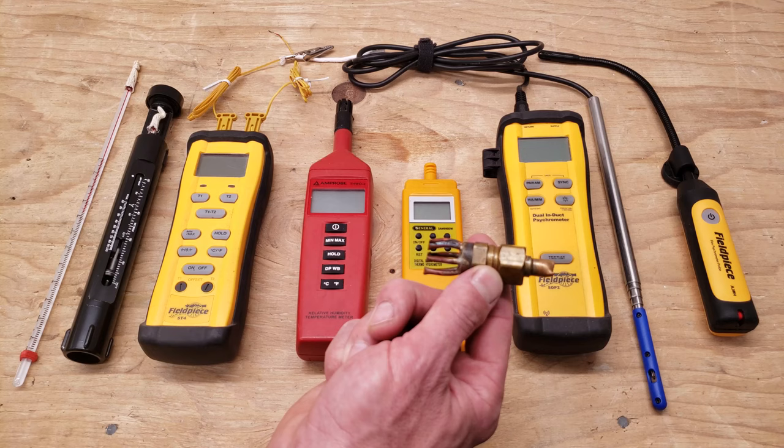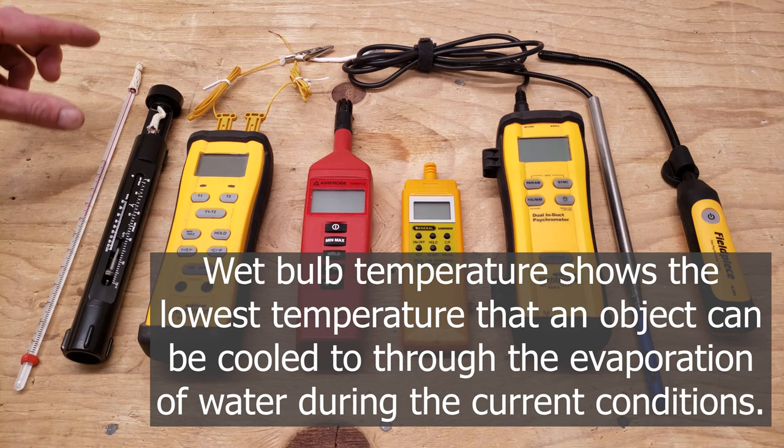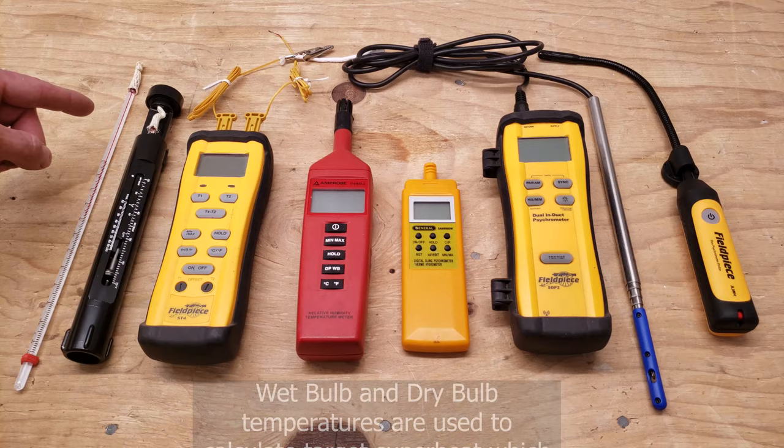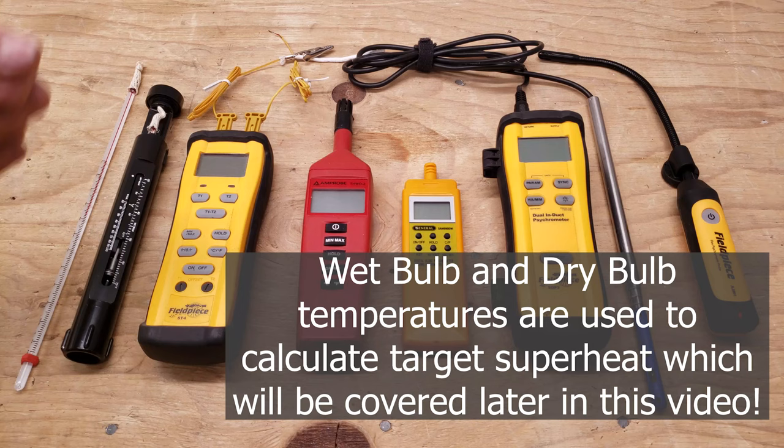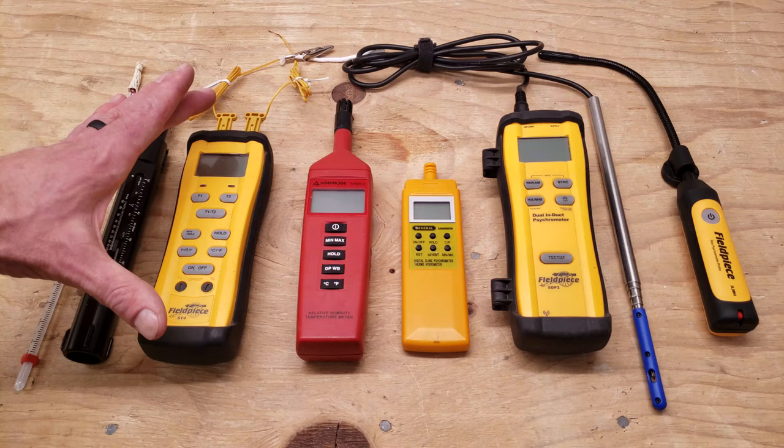To take your wet bulb measurement, you can have a thermometer with a wet sock on the end, and you can put this in front of your return grill where the air is blowing by it or inside of a duct hole. This one right here is a sling psychrometer, and I'll show you that one in a little bit. You're literally swinging it in front of the return grill in order to get your wet bulb temperature.